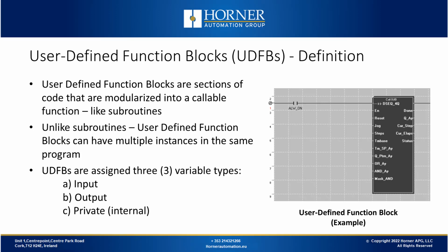For example, if you're going to create a user function block to do some single pump control, and you have a dozen different pumps in your application, you create a single UDFB for pump control. So then you basically have 12 different instances of that UDFB, one for each pump. That's something you can't do with subroutines, because with UDFBs, each instance has its own set of variables.